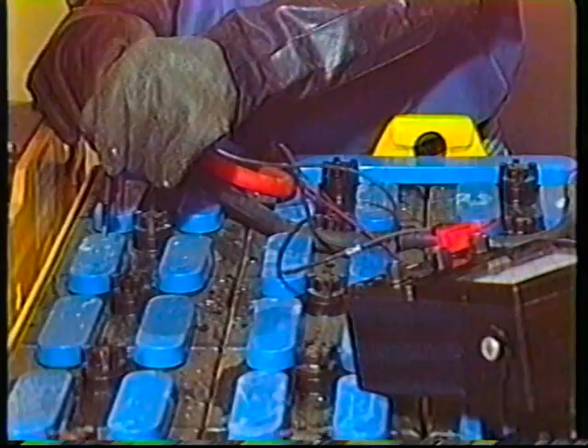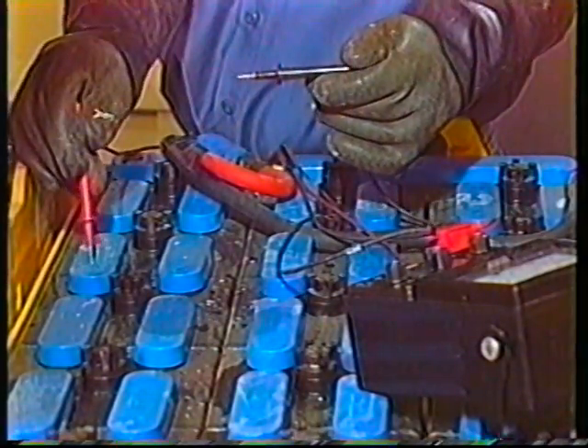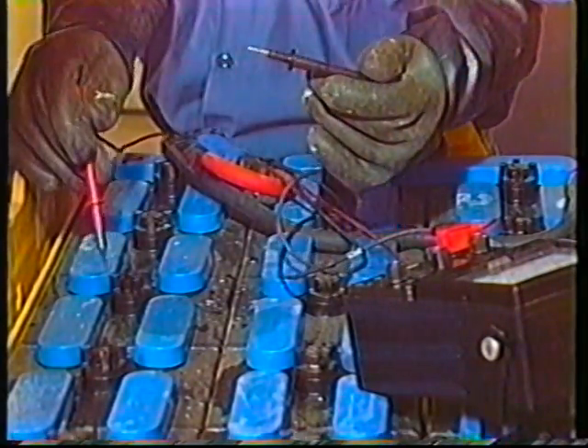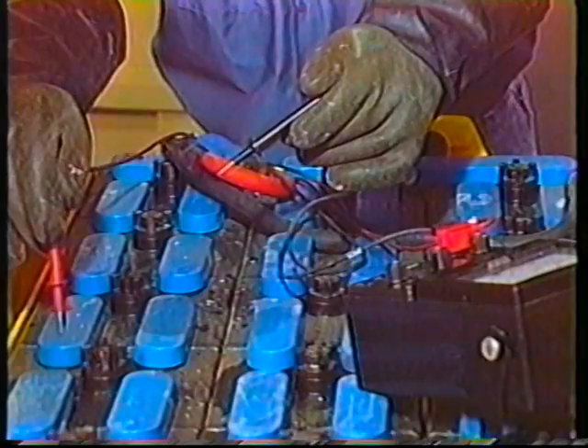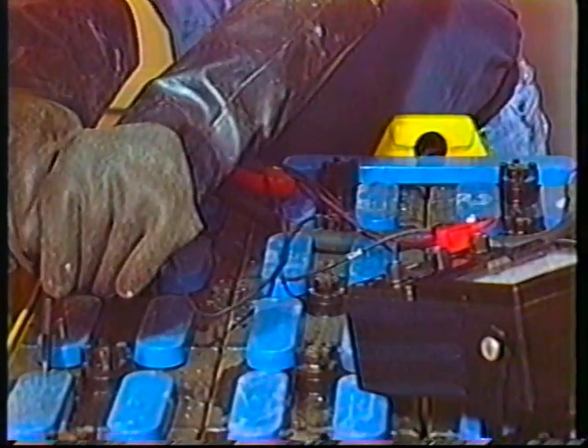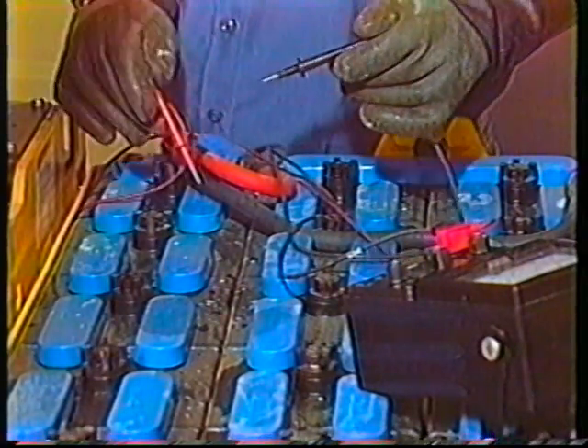Check the voltage drop across each cell using the volt-ohm meter on the 2.5 volt scale. There should be less than 0.05 voltage difference between each cell. If the difference is less than 0.05 volts for each cell, the battery is in good condition. If the difference is greater than 0.05 volts, recheck the electrolyte level and the specific gravity reading. If the electrolyte is okay, replace the battery.